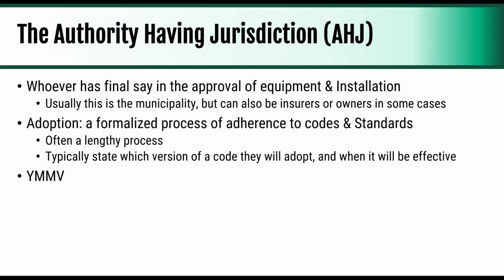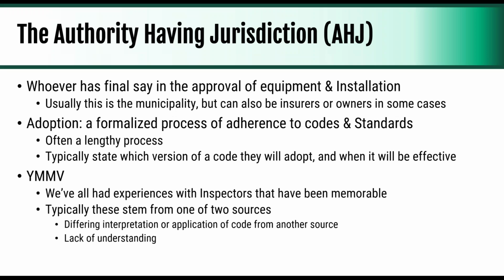This is the AHJ. We talked about this already. They have the final say in everything. And then the adoption process we talked about, but it's a lengthy process. So the example is the NFPA 96 version 2014 was adopted 2 years ago in Ontario, but just effective January 1st, 2020. And again, that's the 2014 standard, so it's already 6 years old. The last thing I'd put is your mileage may vary. We've all had experiences with different inspectors that can be memorable. Most of the problems that we run into stem from two different sources.